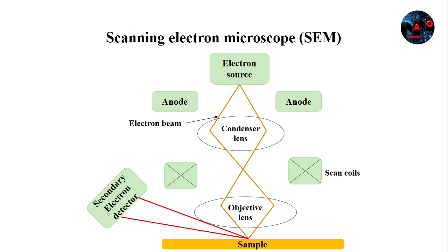High-resolution images are produced by SEM, revealing details of around 1 to 5 nanometers using the secondary electrons. The electron column has scanning coils, and the electron beam is passed through them to the final lens. This deflects the beam in vertical and horizontal directions so that it can perform raster scanning over the surface's rectangular area.